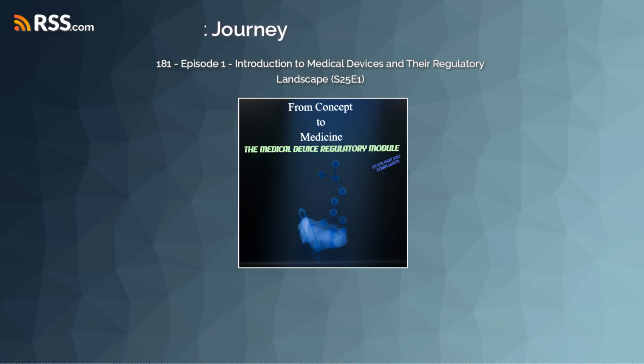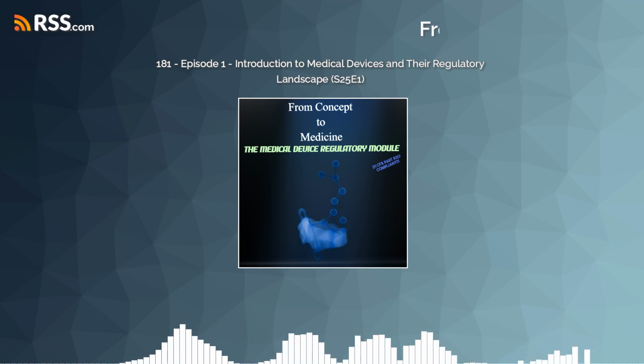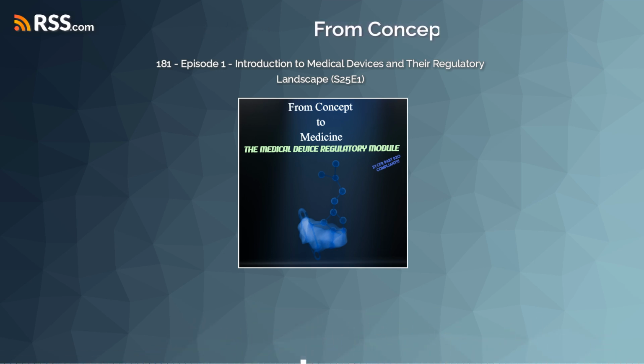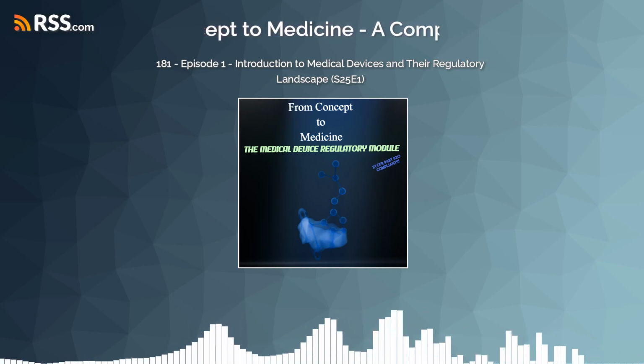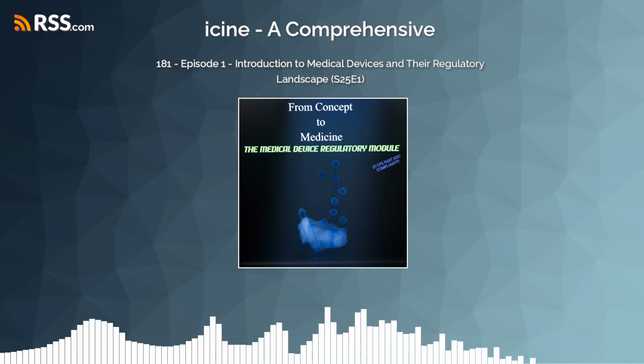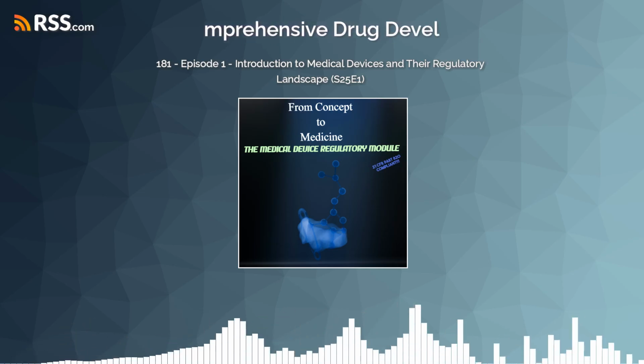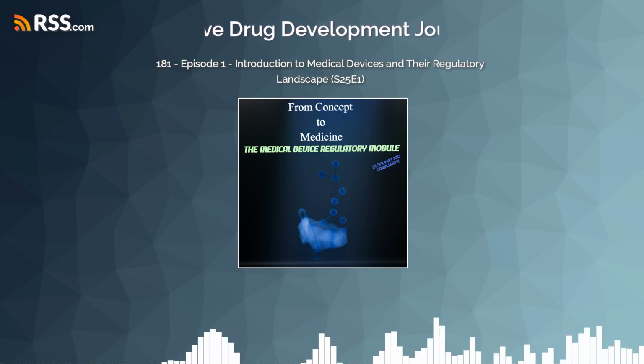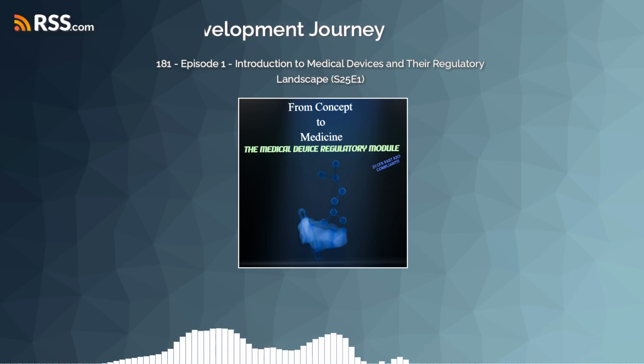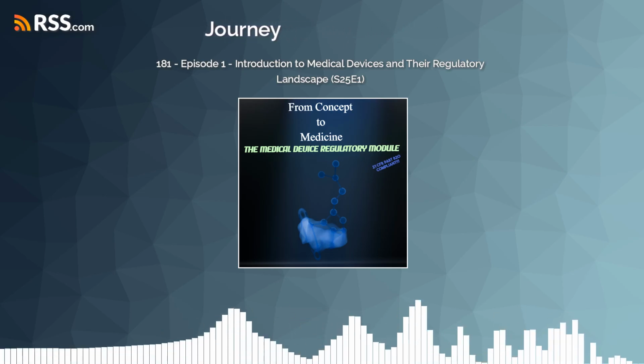Part 11, right. Which has its own stringent requirements for validation, audit trails, security, and ensuring data integrity based on principles often called ALCOA plus. Attributable, legible, contemporaneous, original, accurate, plus complete, consistent, enduring, and available. It's all about ensuring the electronic data is trustworthy and reliable.